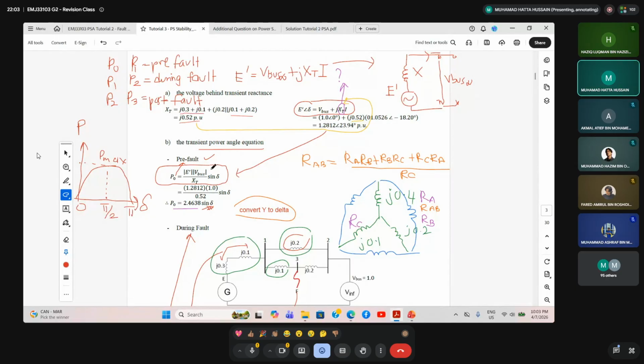From here we can get the pre-fault power. We know E prime is 1.2812, V bus equals the given value 1.0, divided by the transfer reactance 0.52, sine of the rotor angle. So we have the power angle equation for the pre-fault condition: 2.4638 sine of the rotor angle.